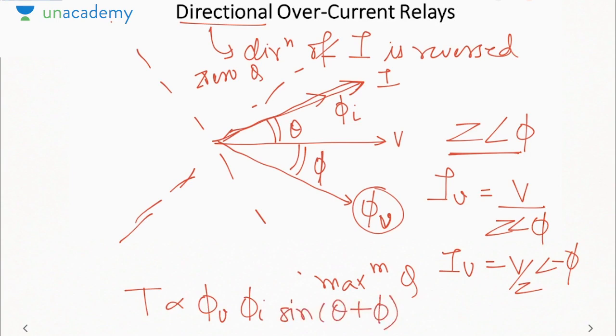How have I directly written this expression? This expression has been written on the basis of the induction disk relay. There I derived that the torque produced in the disk is equal to phi 1 into phi 2 into sine theta, where theta was the angle between the two fluxes. Here the angle between the two fluxes is theta plus phi, and hence the torque will be proportional to sine of theta plus phi. For maximum torque, theta plus phi must be 90 degrees. That means the angle between the two fluxes must be 90 degrees. Is it fine? So that is how this relay will operate.